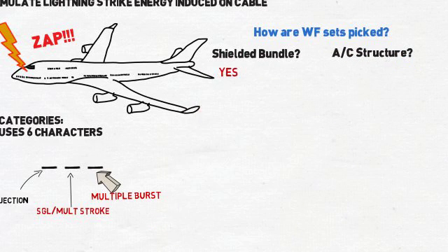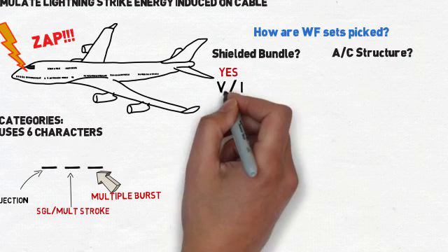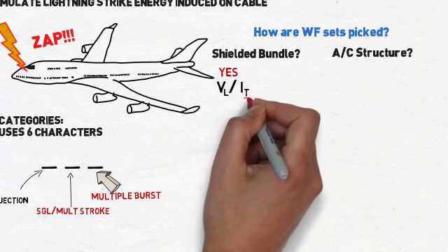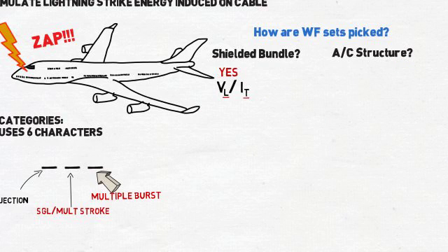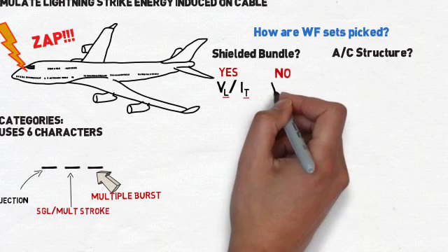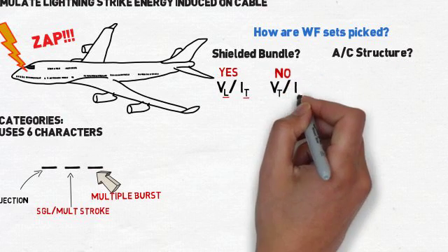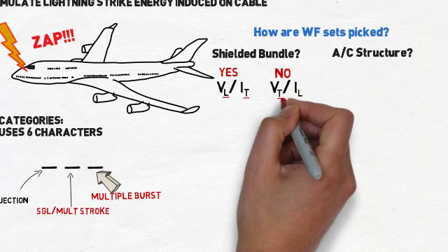If you have any shields in your bundle, you'll likely test to a shielded waveform set, meaning you'll have current waveform test levels and voltage limits. If you have unshielded bundles, it's just the opposite. You'll be testing to voltage waveforms, meaning voltage test levels and current limits.